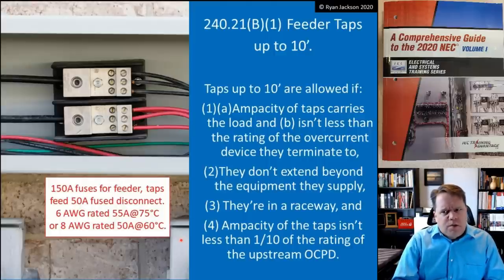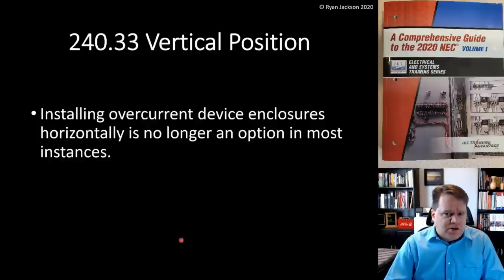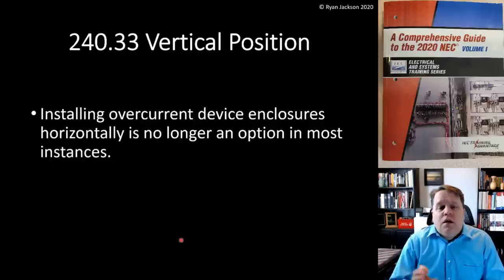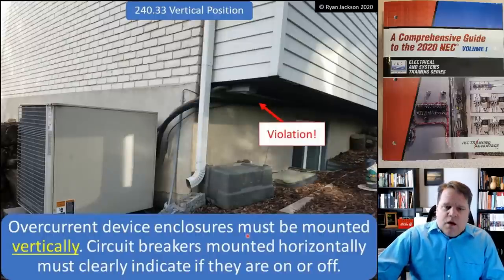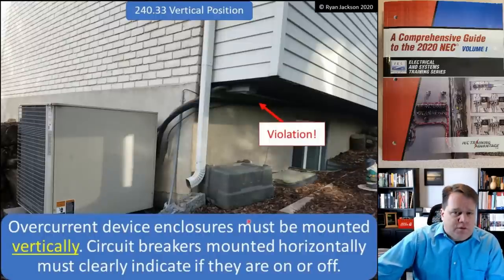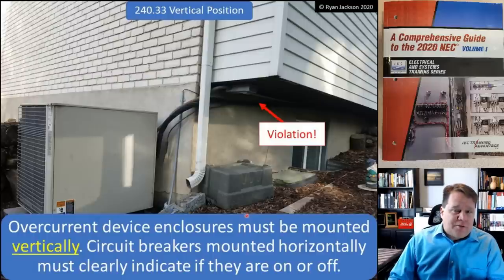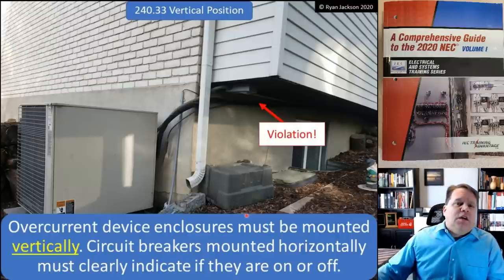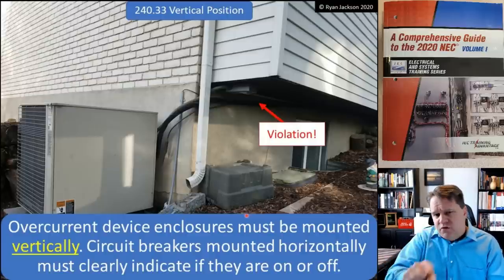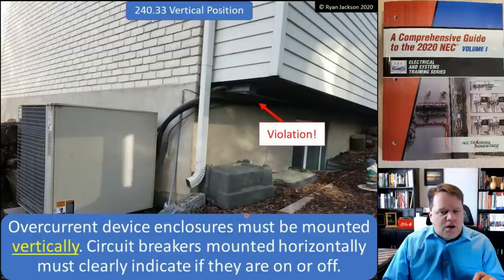Section 240.33 is definitely a technical change: it addresses vertical position. Installing overcurrent device enclosures horizontally is no longer an option in most instances. Overcurrent device enclosures must be mounted vertically. Previous versions of the code said vertically unless impractical. Circuit breakers that are mounted horizontally must clearly indicate if they are on or off.